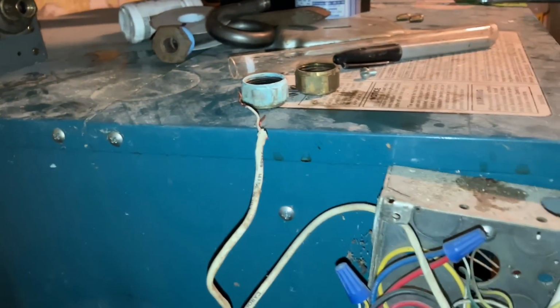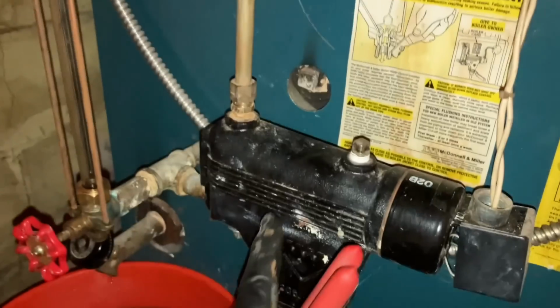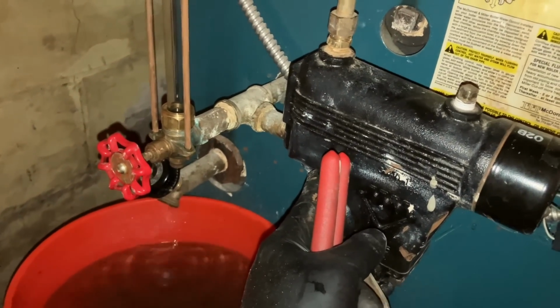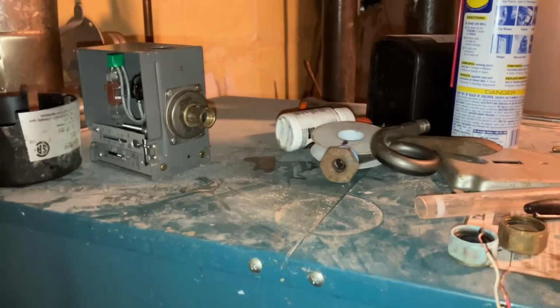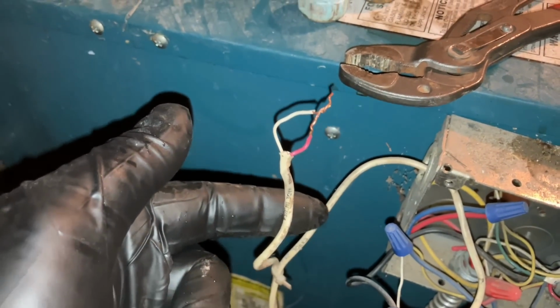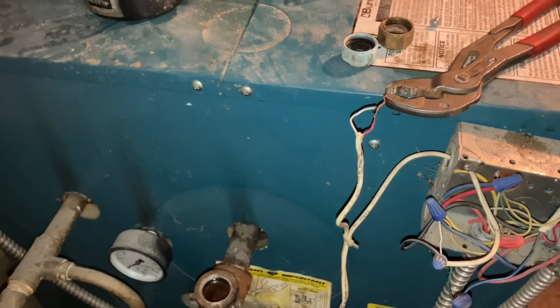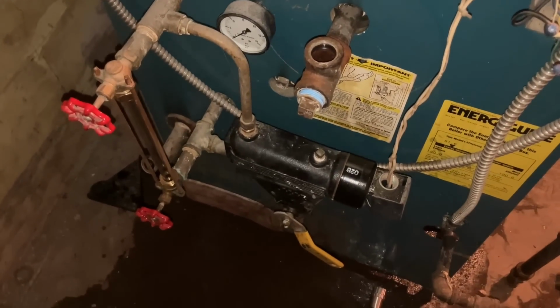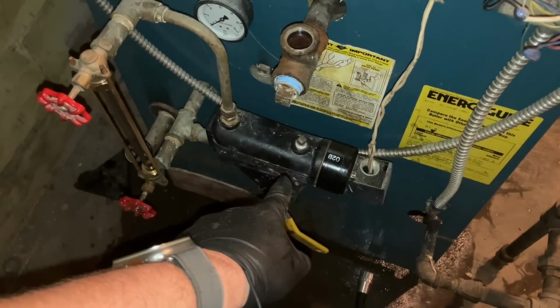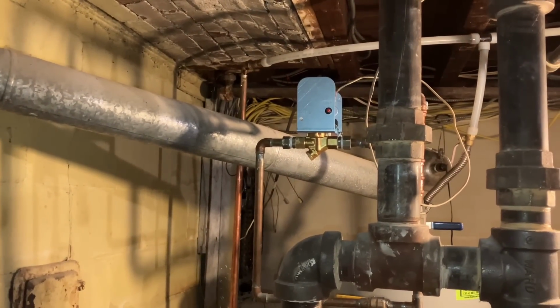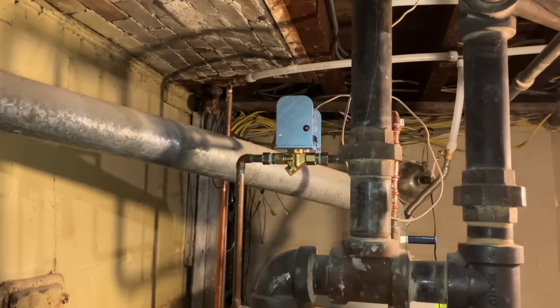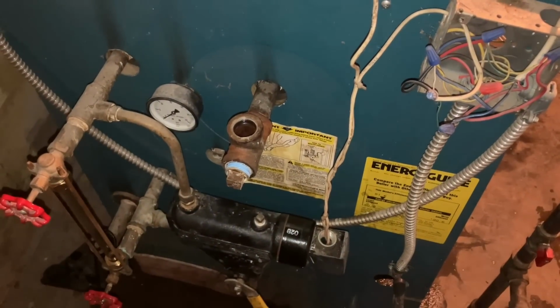So we will jump out, or bypass, our pressure control to make sure that the low water cutoff senses a low water condition. Then we'll reconnect this after we install the Surgex. All right, we jumped out the control wire for the pressure control, and the thermostat relay clicked. That's the humming you hear. Let's see if the low water cutoff senses that low water condition and sends the signal to our automatic water feed, as long as it's wired correctly. That's the $1 million question.